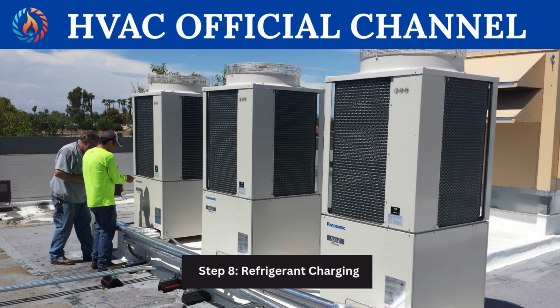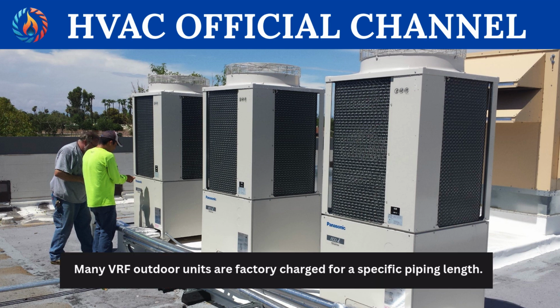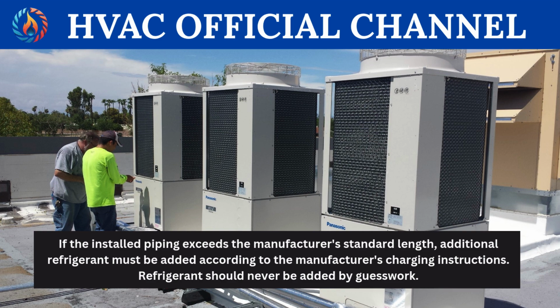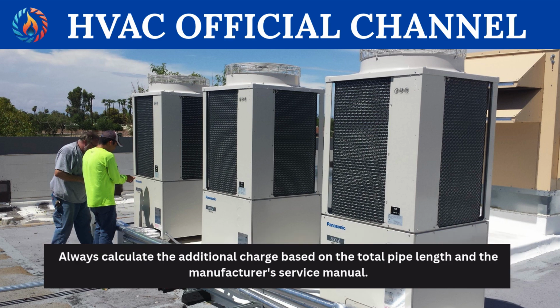Step 8. Refrigerant charging. Many VRF outdoor units are factory charged for a specific piping length. If the installed piping exceeds the manufacturer's standard length, additional refrigerant must be added according to the manufacturer's charging instructions. Refrigerant should never be added by guesswork. Always calculate the additional charge based on the total pipe length and the manufacturer's service manual.